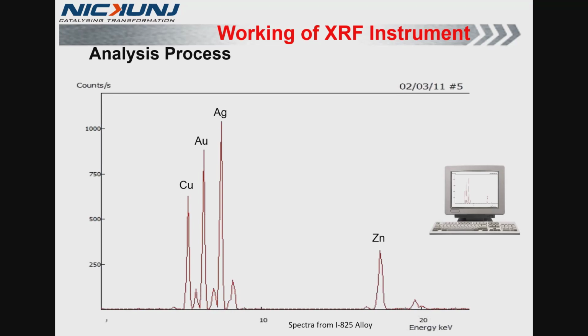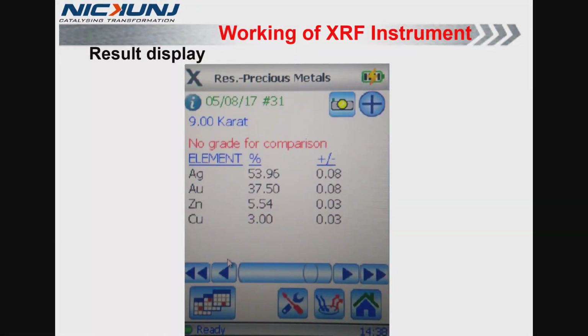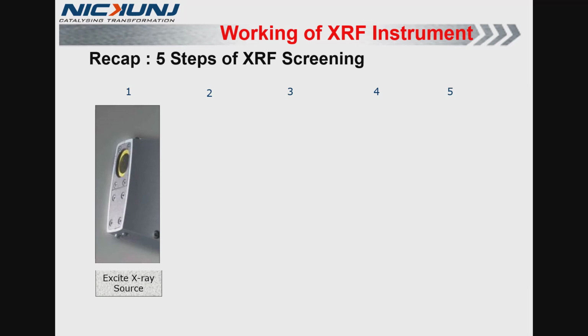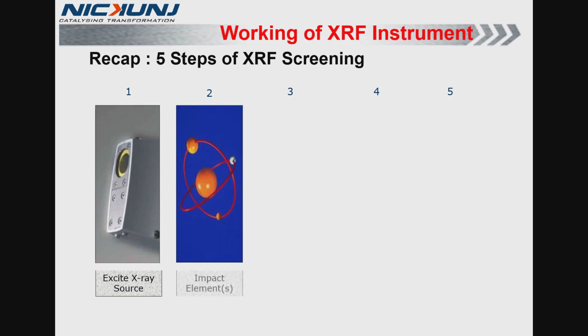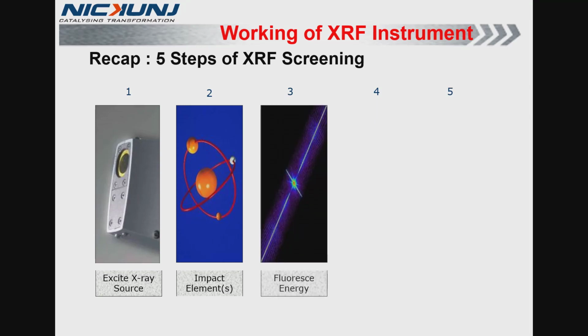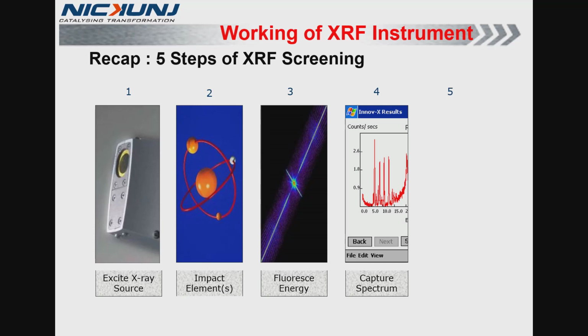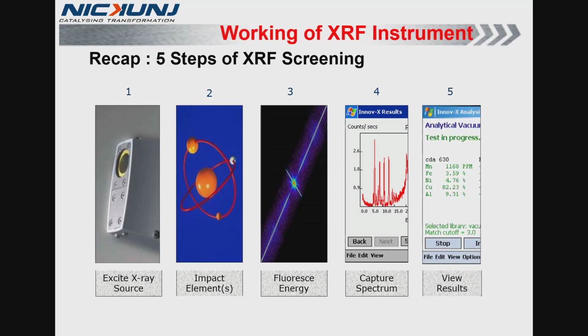During the process of testing, the machine keeps analyzing the data received by its detector for the user specified type. Then the data is processed and displayed on screen as the result of the tested sample. Now let's have a quick recap of the 5 steps of XRF screening. First, the machine excites the X-ray source, resulting in impact on the element. The impacted element releases fluorescence energy. Then our machine precisely captures the fluorescent energy and generates a spectrum. At the end, results are displayed on screen based on the spectrum.